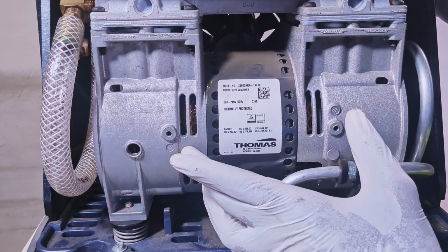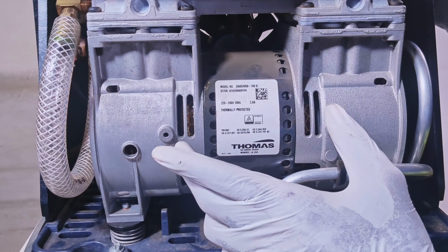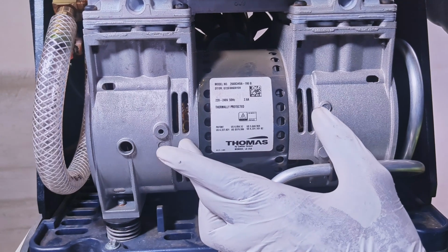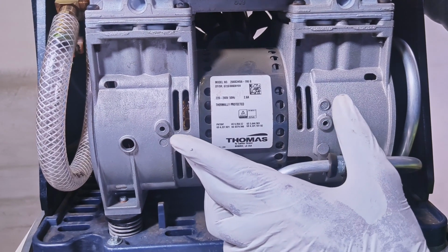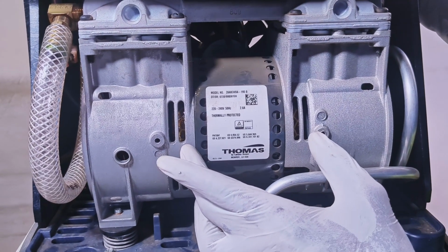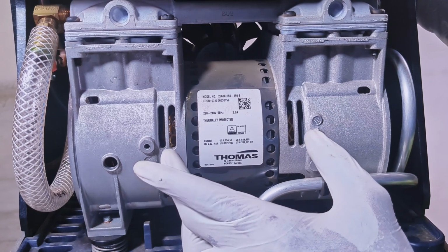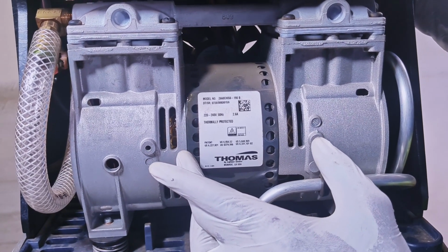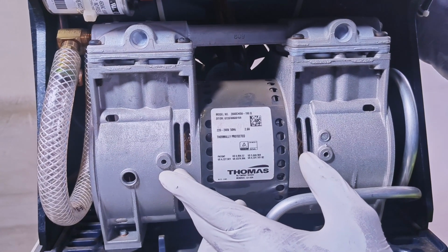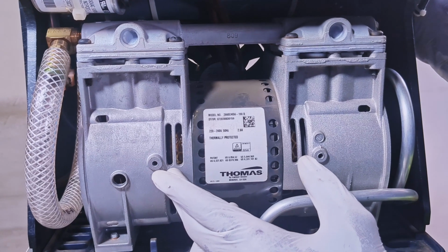On the front side, we have the air compressor. This air compressor is of the Thomas brand 2660 series. It is there to increase the air pressure before pushing it into the sieve beds for oxygen generation. The stator winding of this compressor has a thermostat. The thermostat offers thermal protection to the compressor in cases of high temperatures. This compressor has a pressure rating of 40 psi at a flow of 113.1 liters per minute.